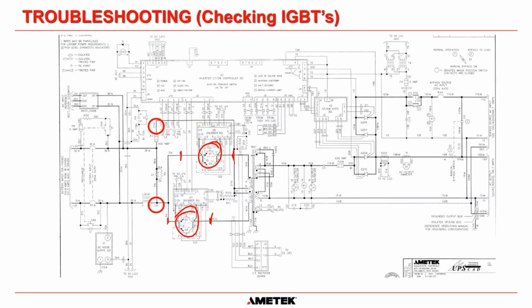In truth, whenever we have an IGBT fail inside an inverter bridge, we always recommend you replace all the IGBTs for 2 reasons. First of all, if one IGBT has failed, then the other IGBT saw high current going through it as well, so we could have significantly weakened it. And the other thing is, IGBTs are made in batches, and we always recommend that the same batch of IGBTs are installed inside the UPS.